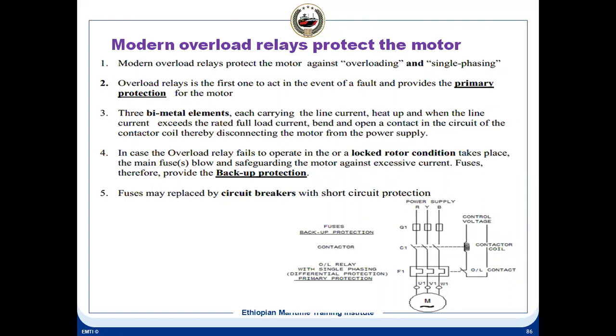And what does backup protection mean? In case the overload fails to operate. There was a question: what is fuse backup protection? In case the overload relay fails to operate, or in locked rotor conditions. What is locked rotor current? Locked rotor current is the current when the motor is just starting. Like in a direct online starter, when you just start the motor, the current at starting is called the locked rotor current.